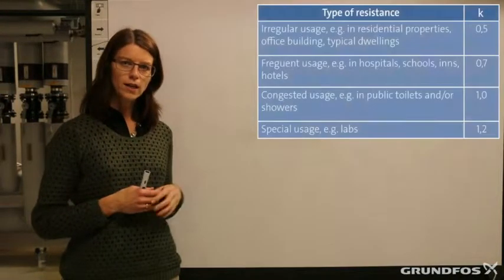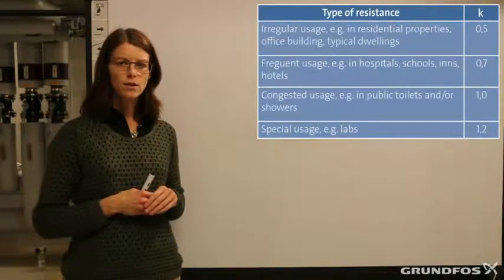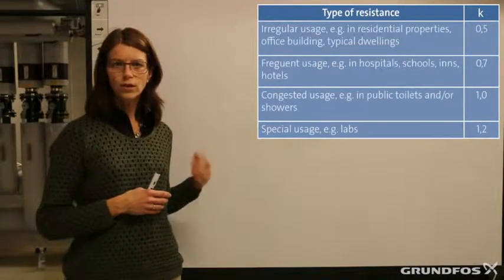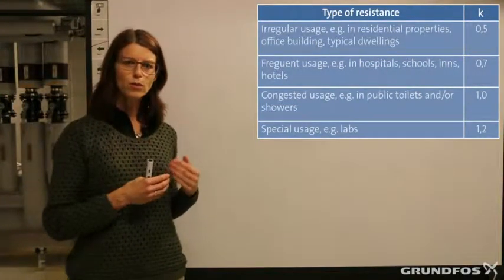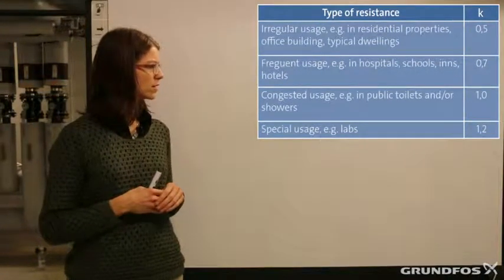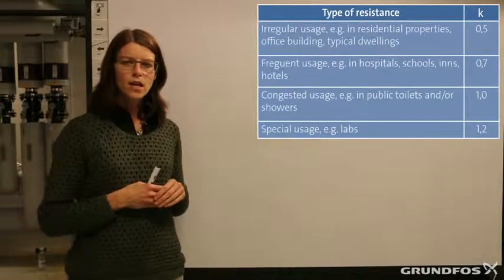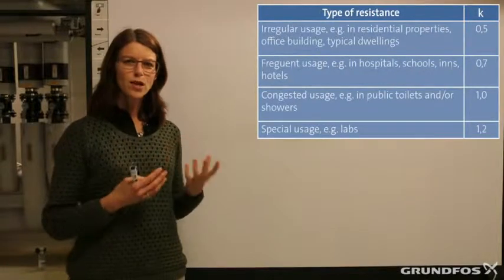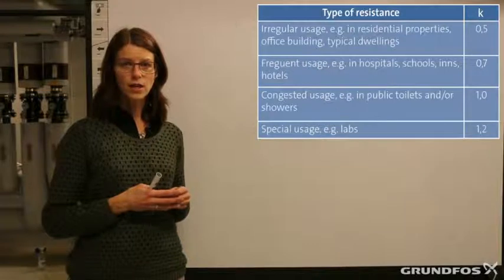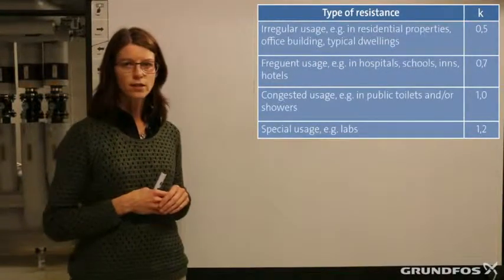When calculating the wastewater flow rate, a K factor must be chosen. The K factor is the frequency factor and it shows the simultaneous use of the different discharge units in the building or in the particular system. In the table shown here you can see different K factors. You will have a K factor of 0.5 for dwellings, as you have a controlled number of people and the frequency of use is lower. Hotels or hospitals use 0.7. For public buildings you will have a frequency factor of 1.0, where you have a more uncontrolled number of people, for example a sports arena. And for laboratories you will have a frequency factor of 1.2.